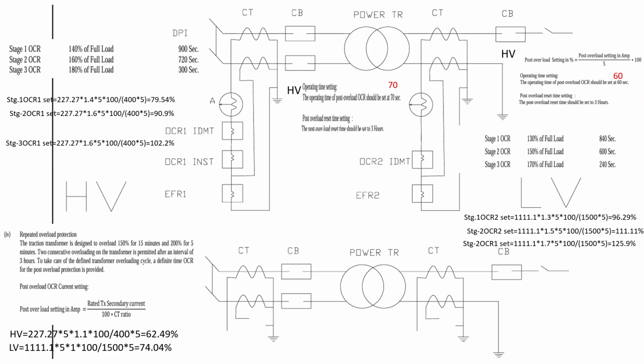We are using two types of isolators, two types of switches. One is a load switch and one is a no load switch. A load switch can be closed or opened from no current to load current, even fault current. During fault current, this load switch will open automatically if it is a circuit breaker assisted with relays. But there is another load switch in our system, the interrupter, which will not open automatically. The CB will open and make the circuit dead, then you can operate it again. So the CB is associated with relays, and it trips automatically during any fault.